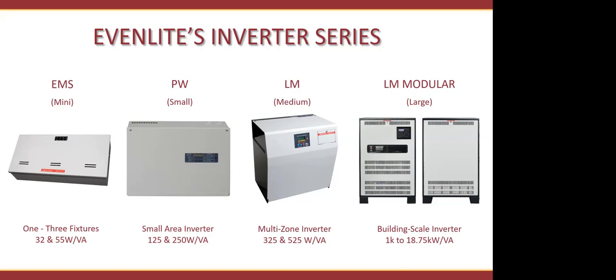And the greatest thing about this is that if you think about how you need to swap out battery packs or test individual fixtures, if you're using battery pack fixtures, quite often that shuts down the workspace. With an inverter, you do not have to do that because this testing is done in one centralized location. There is no maintenance required for swapping out battery packs, and you can literally leave every location up and running and not require occupants to exit the area to do the required fire testing.